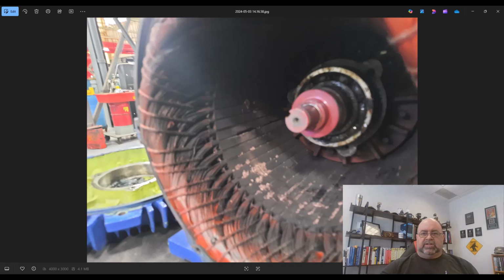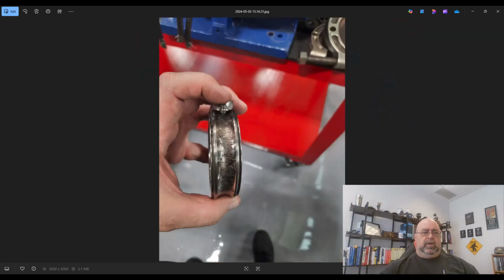That bearing didn't open. So hold on a second—in this one, you can see that opposite drive end bearing. Pretty much the balls were shot, the inner race was gone, the outer race was gone, and the drive end had major fluting. The challenge I have with this is the vibration system had said this motor was in perfectly good condition. We did also note that the grease was burned and dried because of high bearing frequencies. None of this was captured, including the belt application or the belt issue that was going on, which also contributed to all of this.